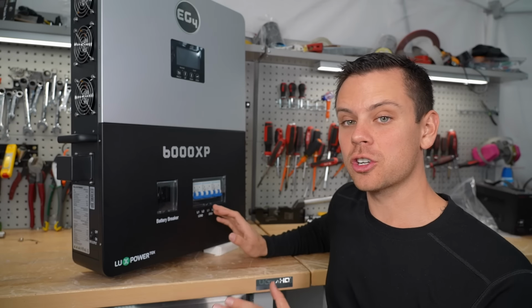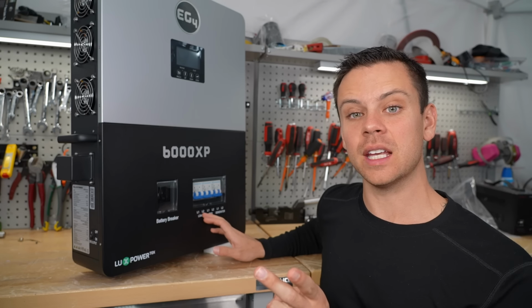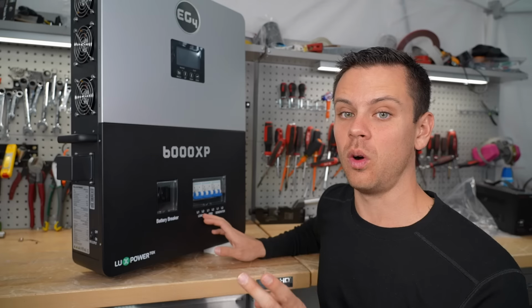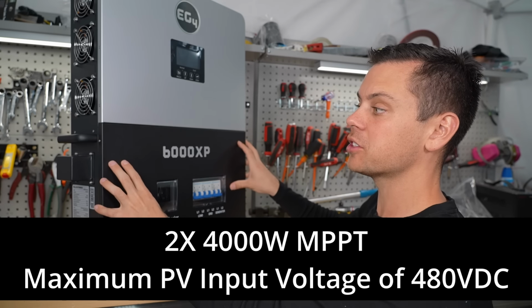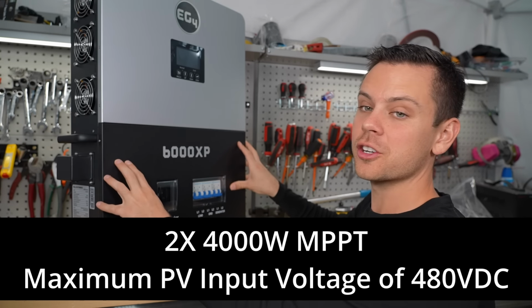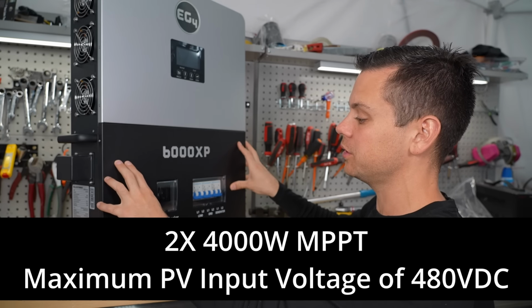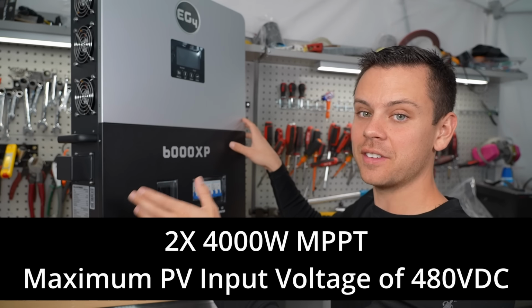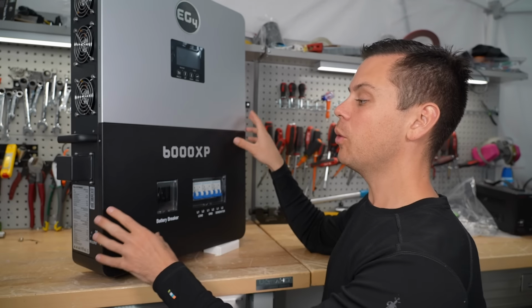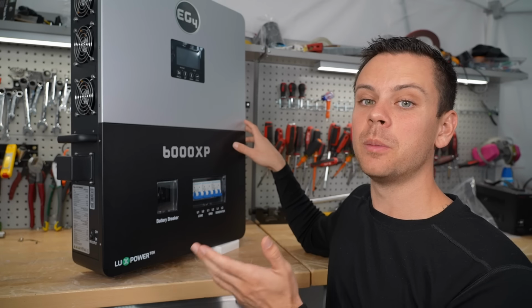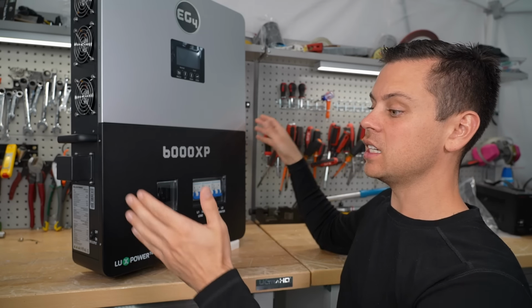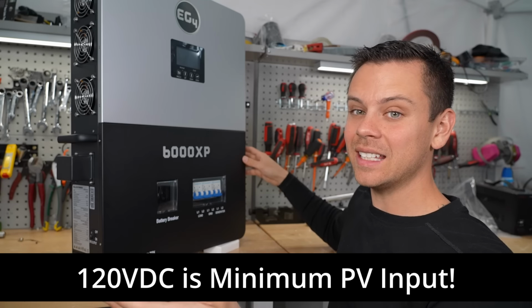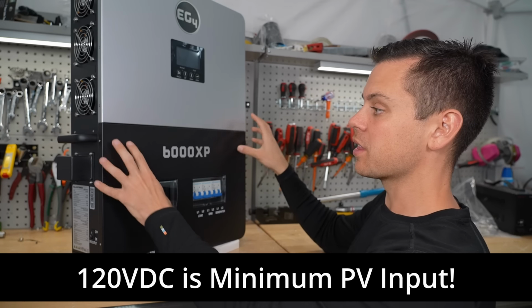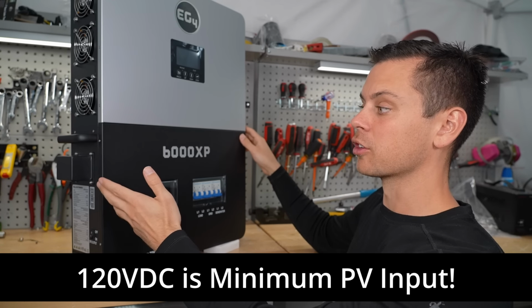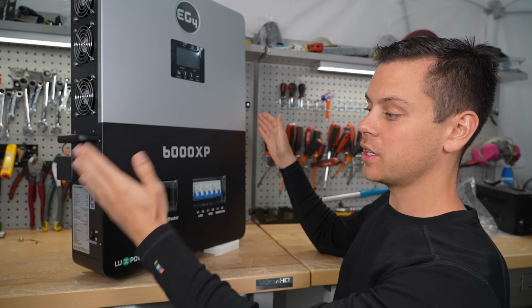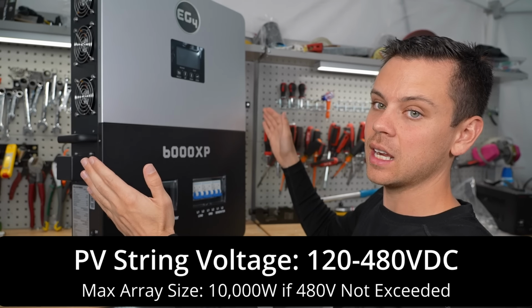Now let's talk about the solar charge controller. There are 2 trackers, or 2 PV inputs, and each one can handle 4,000 watts. So the maximum input is 8,000 watts of solar panels, and that's at 480 volts maximum PV input voltage. And that circuit is 99% efficient, but that's pretty common for MPPTs. Now what you do need to know about the MPPT is the minimum operating voltage. So you need to have enough panels in series to create at least 120 volts DC for this to start charging the batteries and running the inverter with that solar power. So the voltage range is 120 volts DC to 480 volts DC.